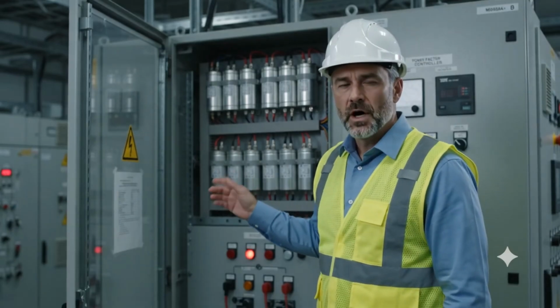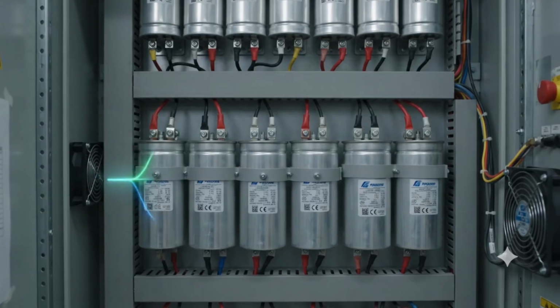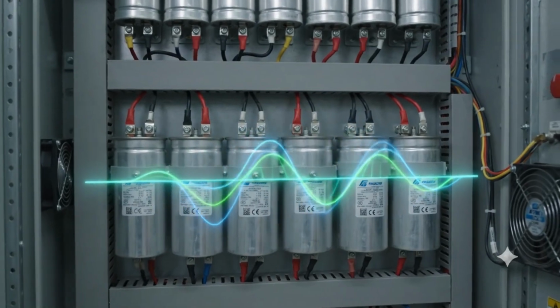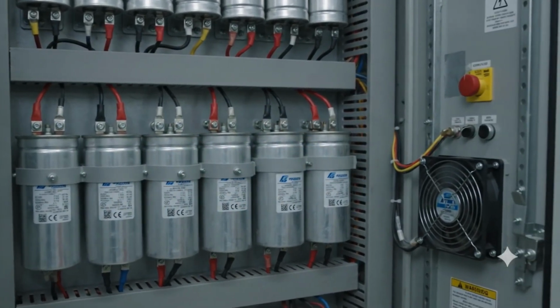The culprit? A recently installed capacitor bank meant to save money on power factor penalties. It was a classic harmonic trap.